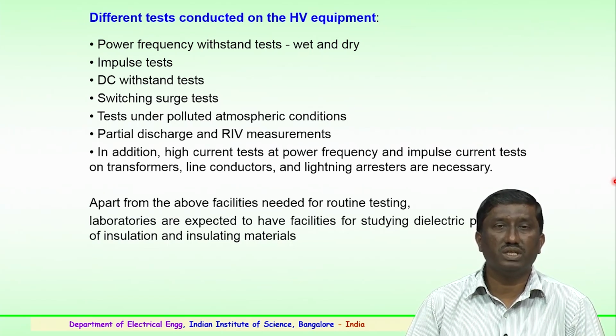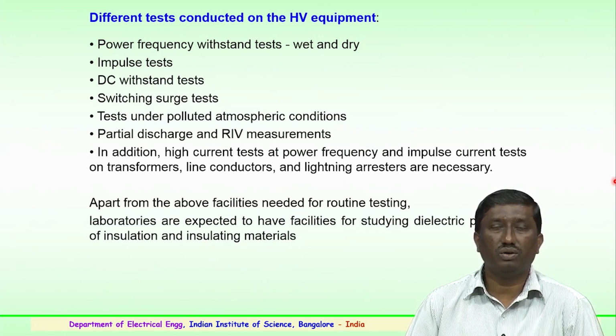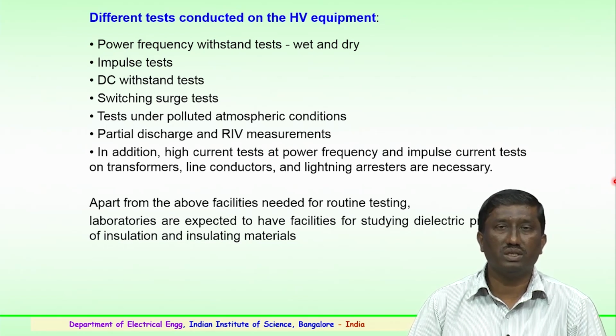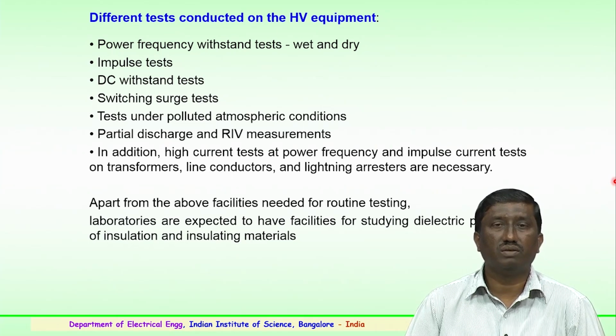You have the switching surge. Switching surge for voltage applications is 250 by 2500 microseconds. In case of lightning arresters it could be 30 by 60 microseconds.